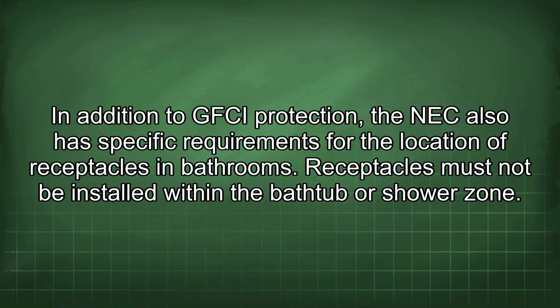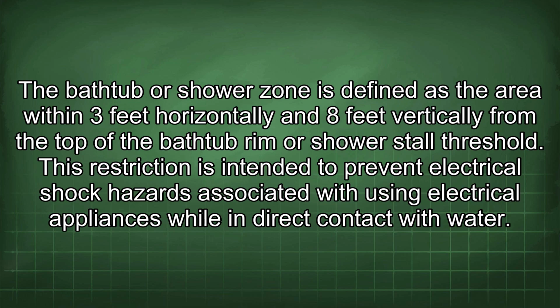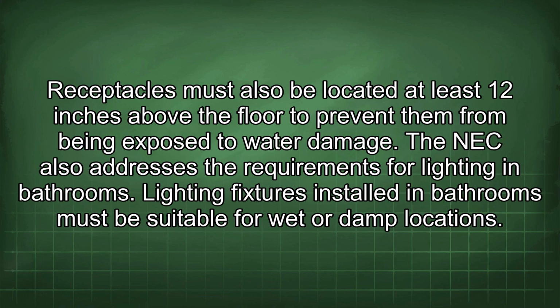In addition to GFCI protection, the NEC also has specific requirements for the location of receptacles in bathrooms. Receptacles must not be installed within the bathtub or shower zone. The bathtub or shower zone is defined as the area within 3 feet horizontally and 8 feet vertically from the top of the bathtub rim or shower stall threshold. This restriction is intended to prevent electrical shock hazards associated with using electrical appliances while in direct contact with water. Receptacles must also be located at least 12 inches above the floor to prevent them from being exposed to water damage.